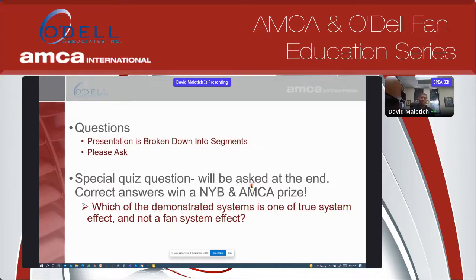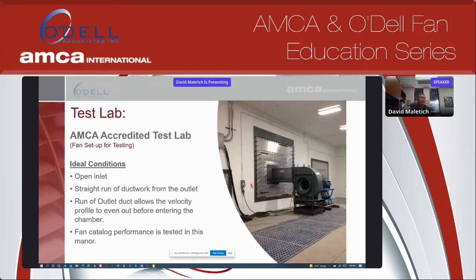So let us know, and we'll definitely send that out. Here we have a fan in an AMCA accredited lab, and this is how all fans are pretty much tested in accordance with AMCA standards. This is a figure 12 configuration. We have a fan with an open inlet. That open inlet has an inlet bell on it that uniformly loads the wheel and minimizes entry losses into the fan. Discharge side of the fan, we have a straight run of ductwork. That straight run of ductwork allows for the velocity profile of the air as it discharges the fan to even out before it enters into the bulkhead and into the test chamber.